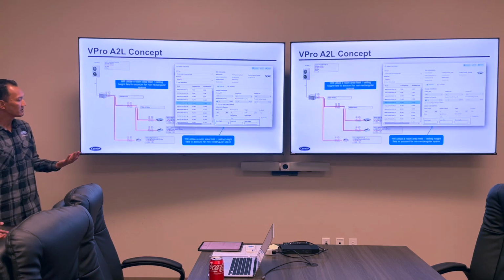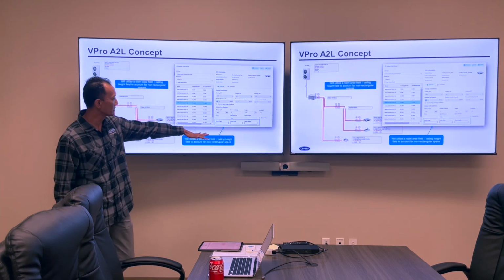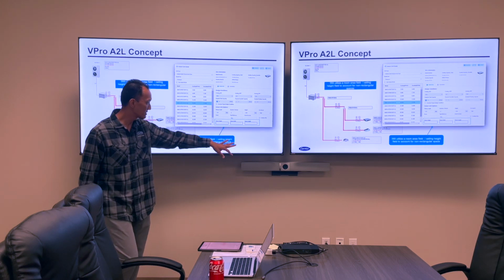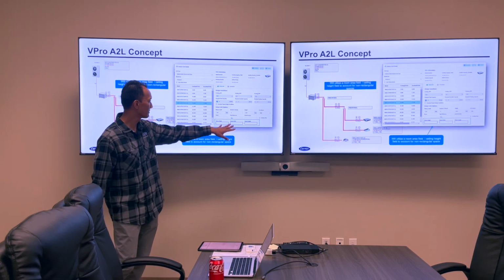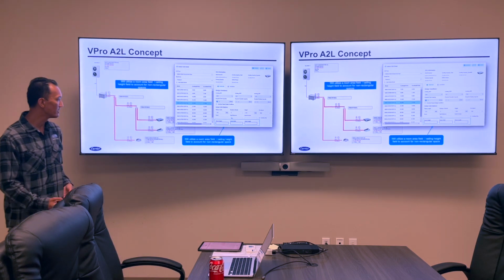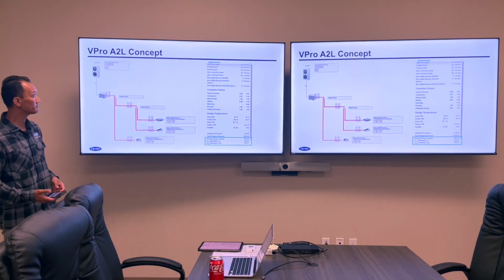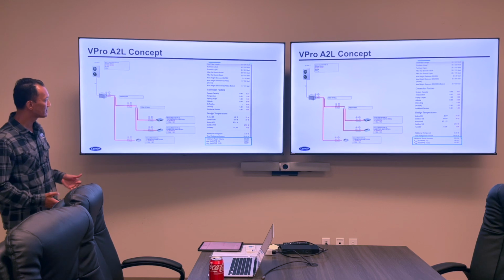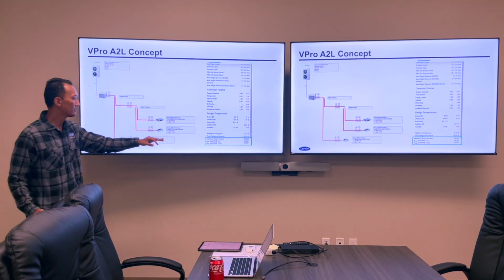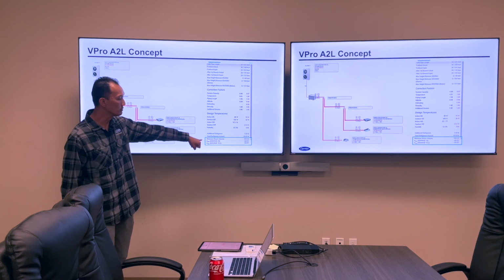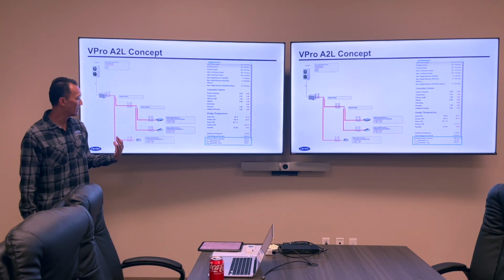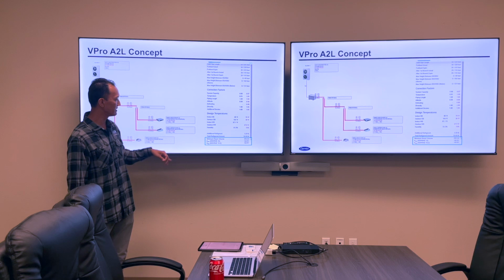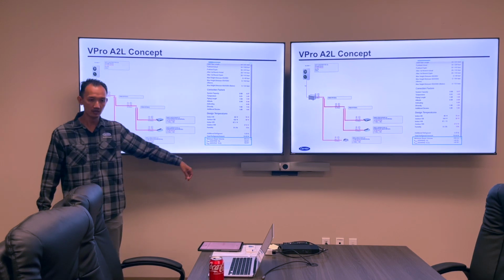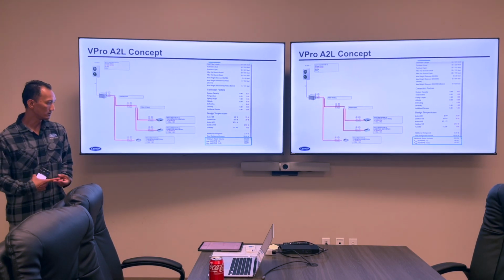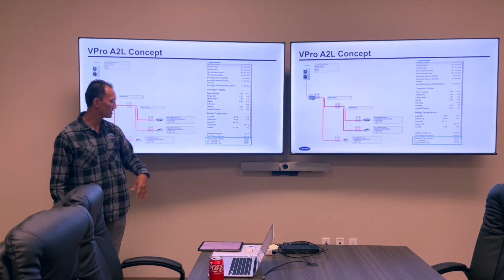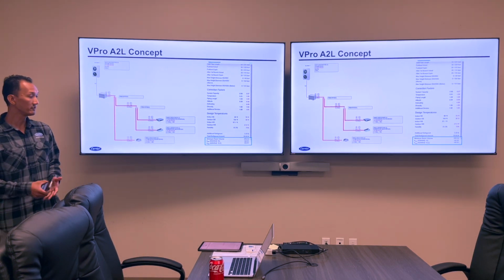So what that does is our software will ask for the dimensions of your room, and then based off of all those parameters, if we plug everything in, our software will tell us the minimum room volume that's allowed, given the amount of refrigerant in the system, and it'll give us the minimum area for either a commercial or residential application, based off of ASHRAE 15 or 15.2.